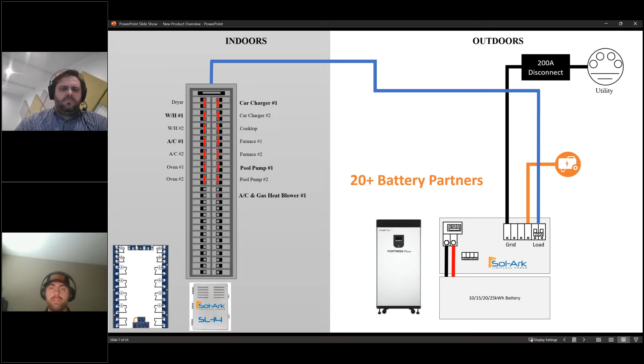So here in this diagram, you have the 15K connected to the main panel. You have the grid via a 200 amp fusible disconnect to meet NEC code, and then you have the smart load. Those 3 items are really all that you need to suffice a 200 amp service, allowing you that customization and feasibility in the event of an install, and allowing you to do more installs without the hassle of dealing with multiple pieces of equipment.